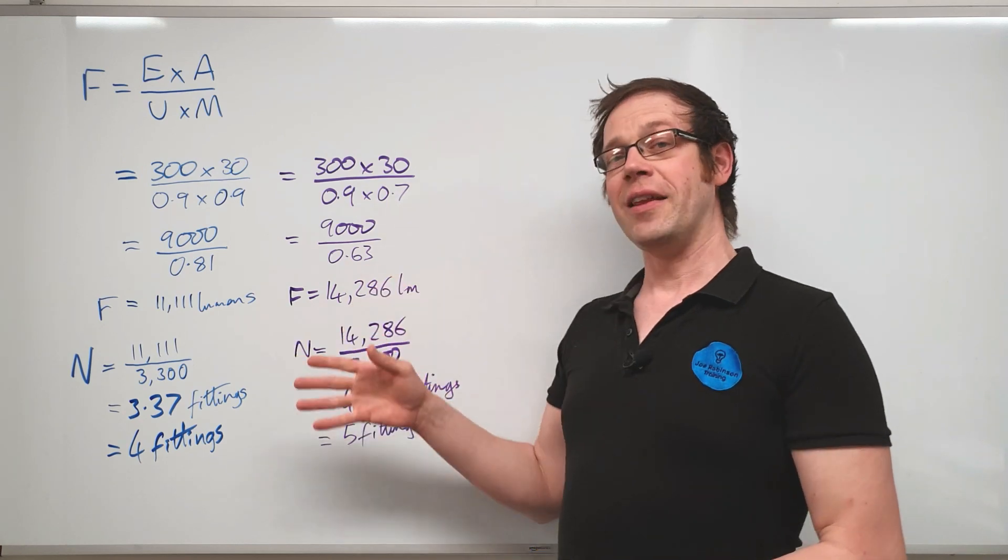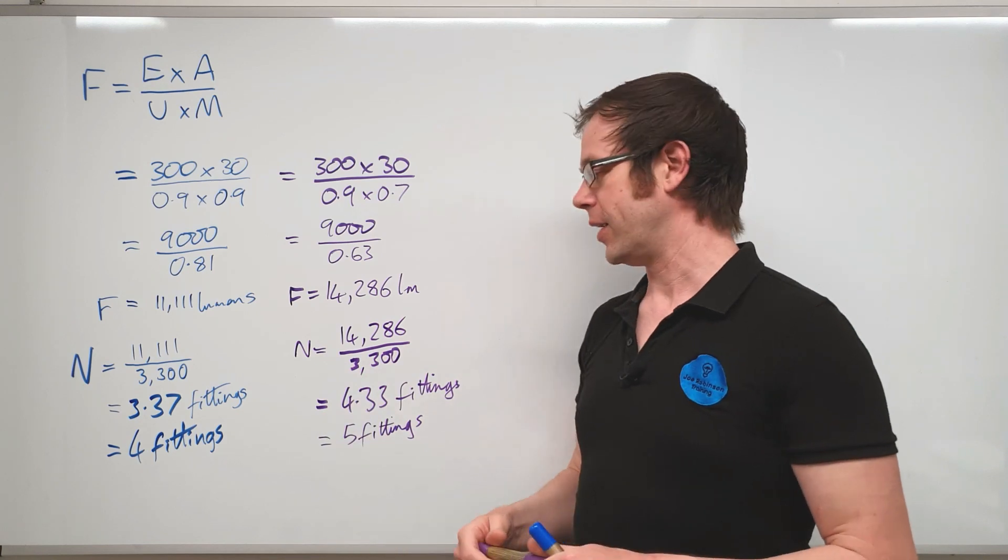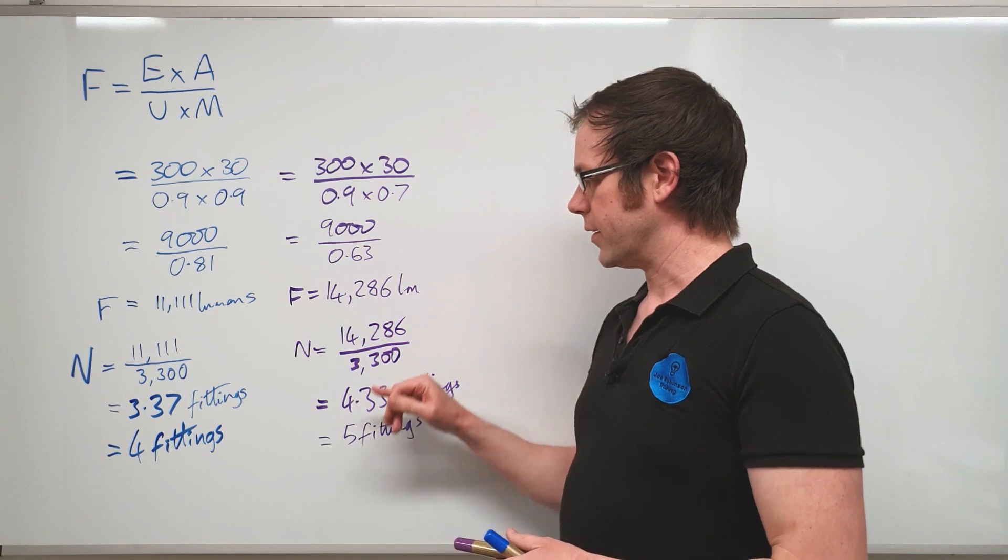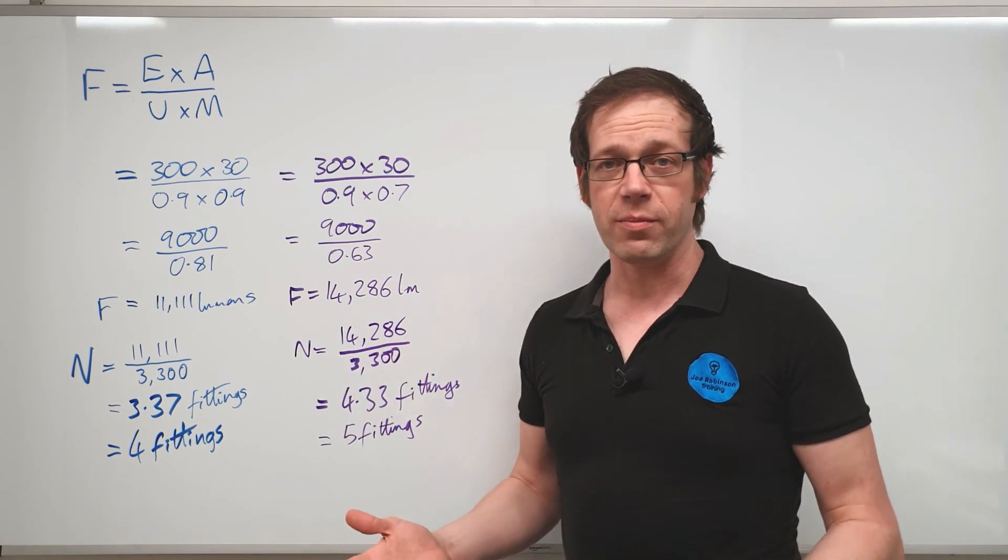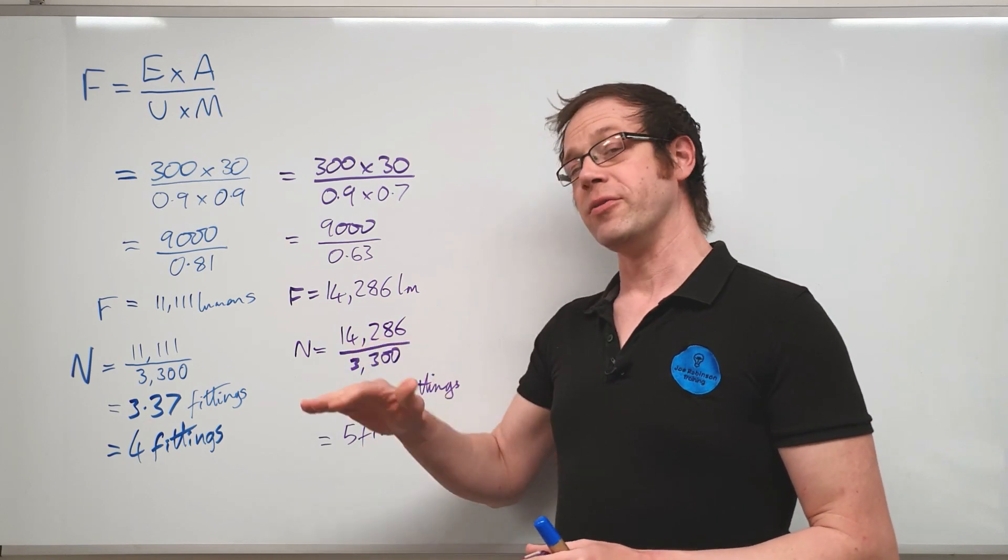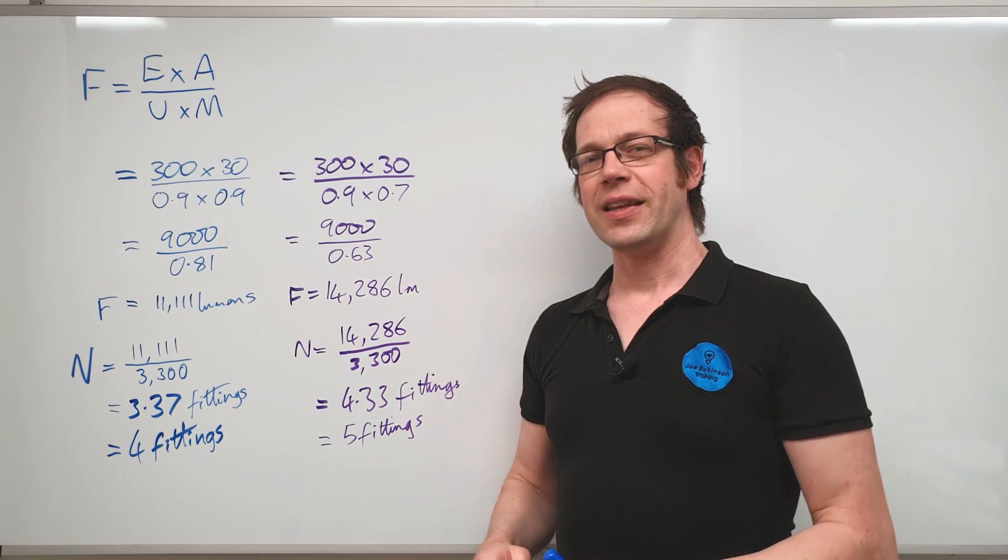So you can see the challenge that we're up against already as lighting designers when we start doing these calculations. As electricians there's a number of ways around it. You might go to six fittings and install dimming technology, that could be a requirement of the installation anyway in order to bring the illuminance down to the right level. However it's quite a knotty problem for us to deal with and it's a little bit beyond the scope of this video.